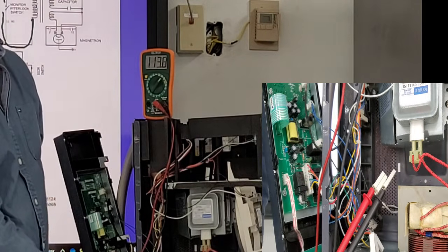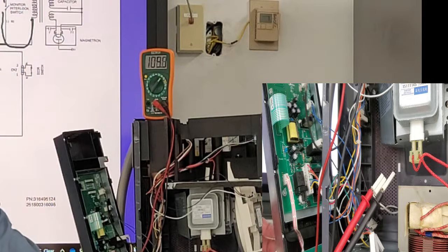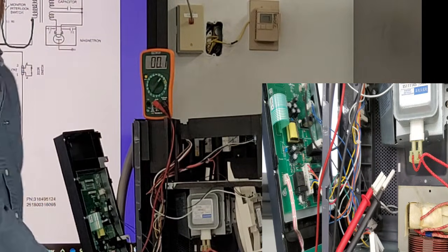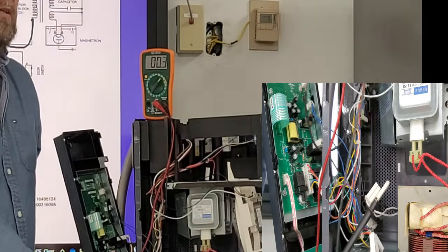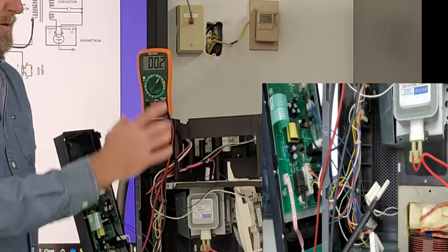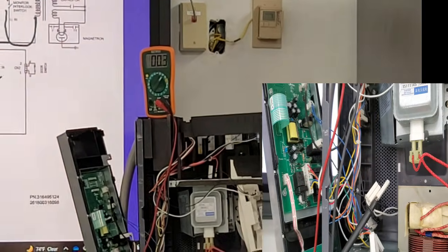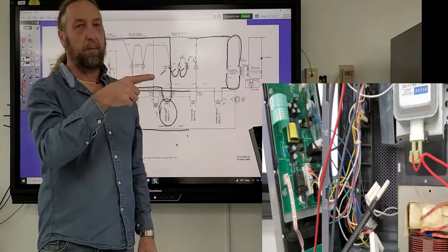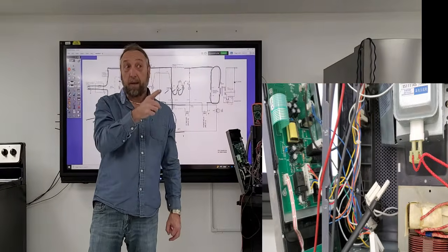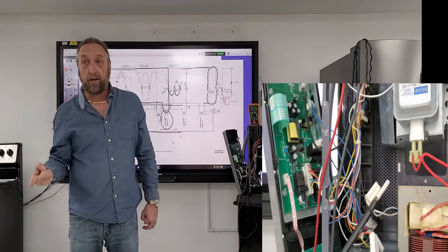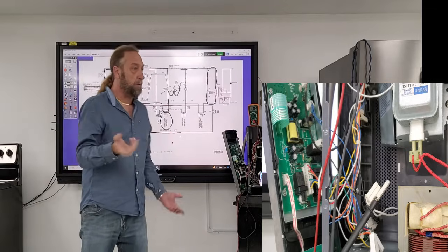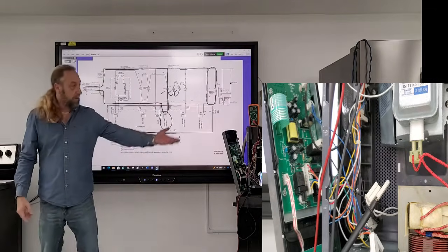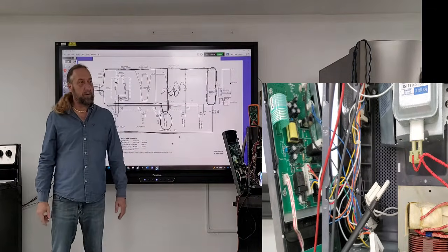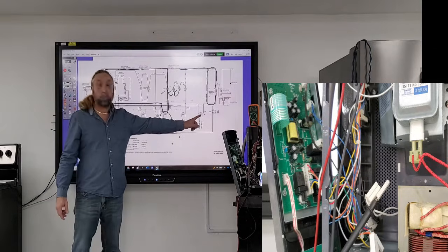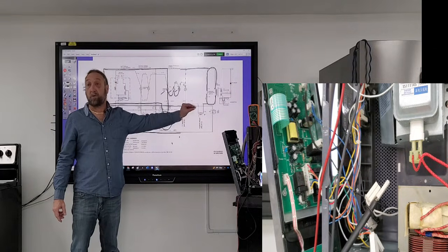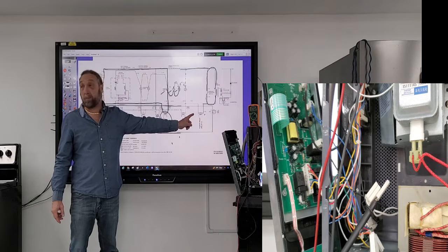I got voltage. When I press stop, the voltage goes away. So what does that mean? You mean the transformer's good? No, it doesn't mean the transformer's good, it means you're getting 120, getting power. It means I'm getting power, but what does that mean? The monitor is good? No, the monitor's not even in, I've got the monitor sitting on the table. It means that relay number 2 on the board is closing, and the problem is not my board.